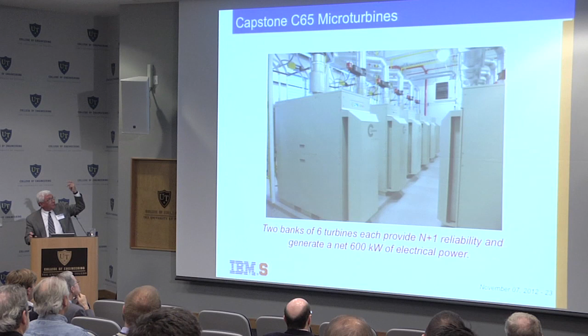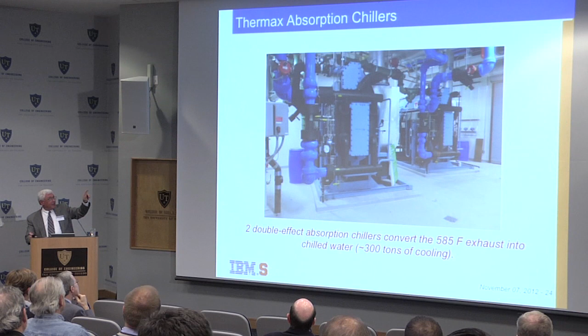You saw this picture. These are the 12 Capstone turbines. Roger showed this picture. The exhaust from those is collected and piped to the room next door. Each 6 of the turbines are ganged together, and they feed one of these 2 absorption chillers. These are double effect, 2-stage absorption chillers. They have a thermal COP in excess of 1.3. In other words, for every unit of heat you put in, you get 1.3 units of cooling.